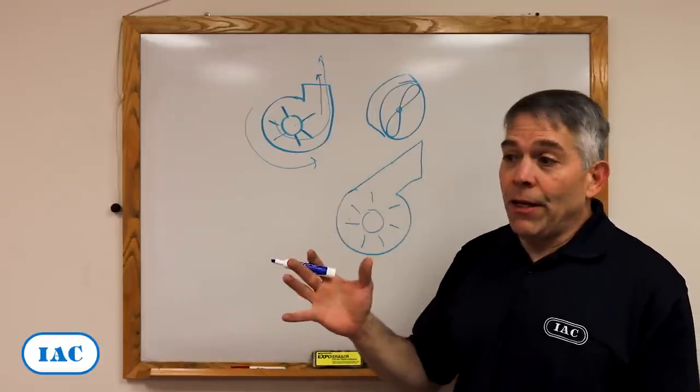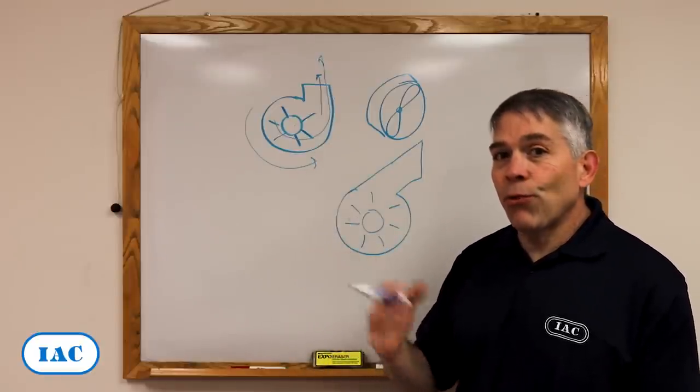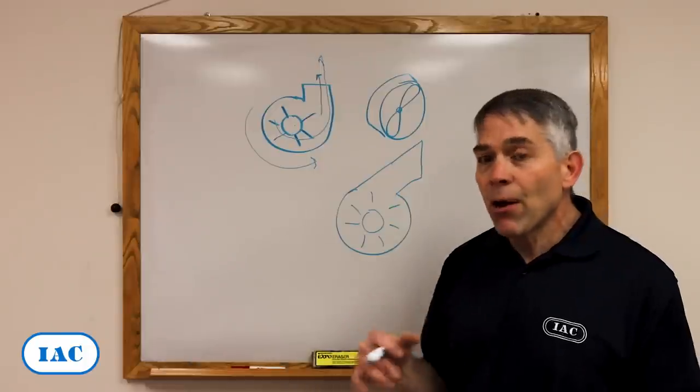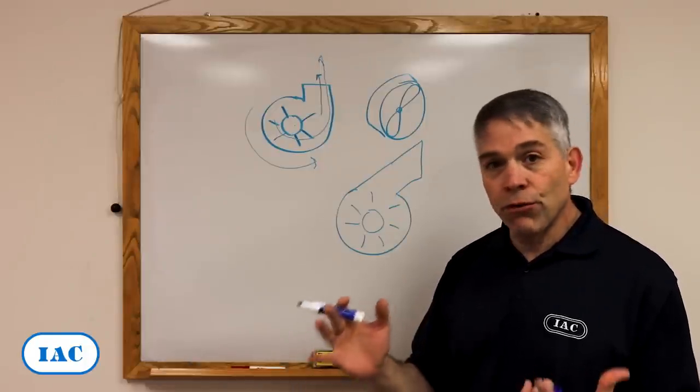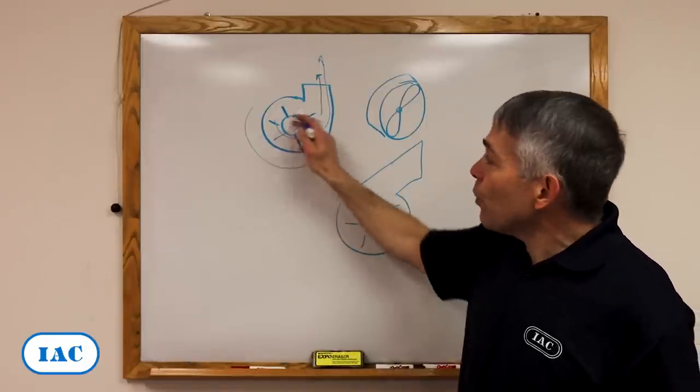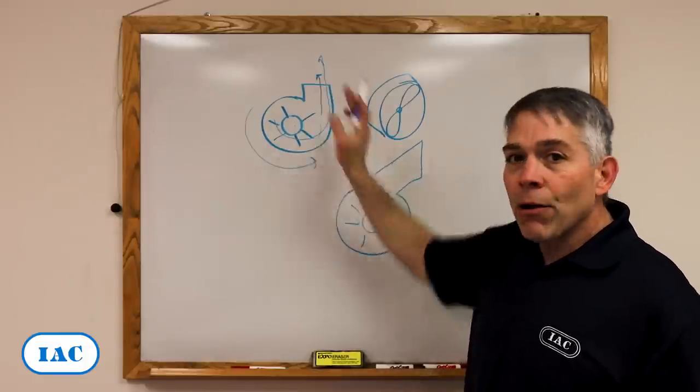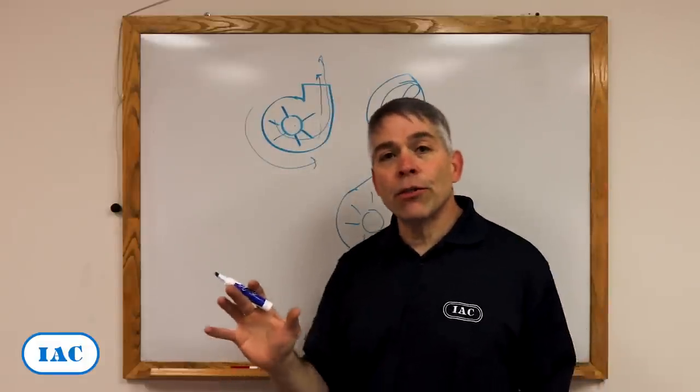Now, it's easy to see that people think that if the fan is rotating the wrong way, it would blow backwards. But that is not the case with centrifugal fans. If this wheel is rotating the wrong way, it'll still blow air out, but at a very inefficient mode.